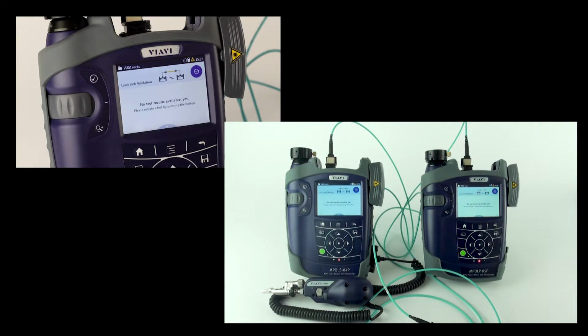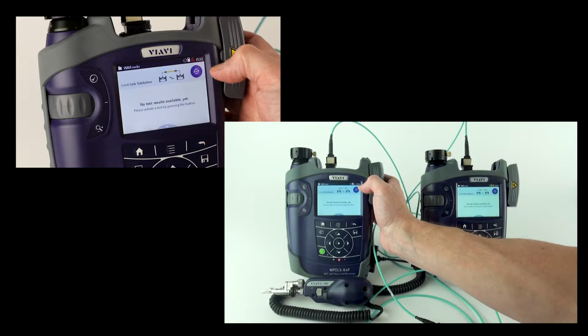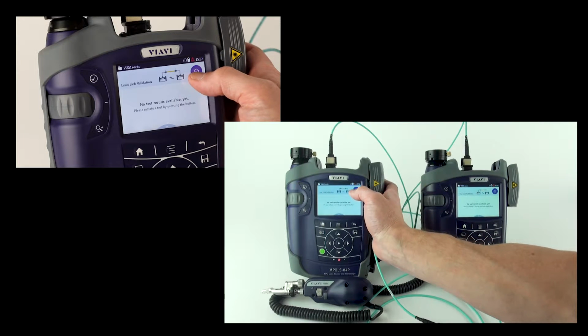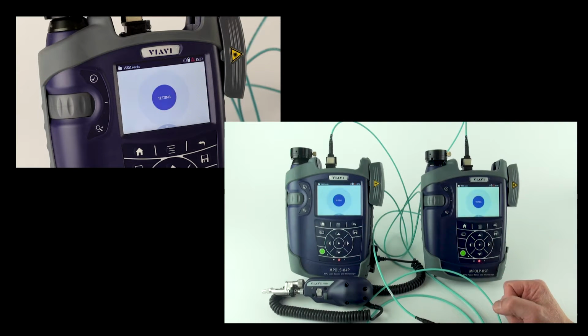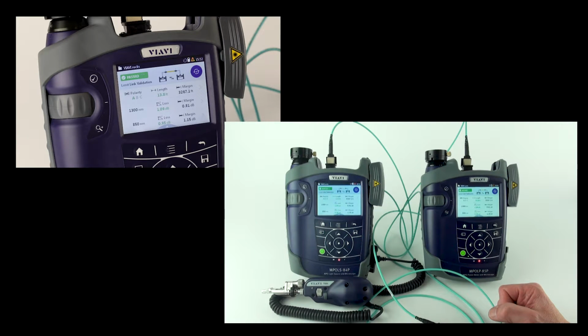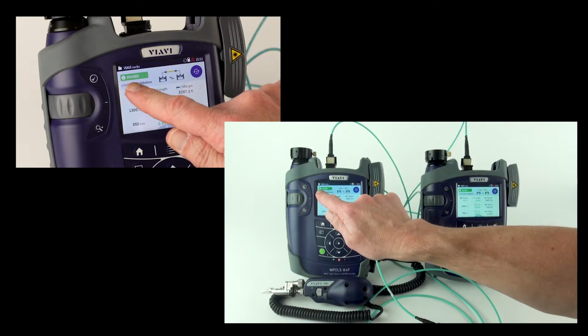All right, so we're trying to get a pass here. So we've done our set reference, and now all that you need to do when you've added in everything and connected up to what you're testing is press the auto test button. It takes somewhere around 6-8 seconds to test all 12 fibers, loss, length, and polarity, and then gives you a test result.